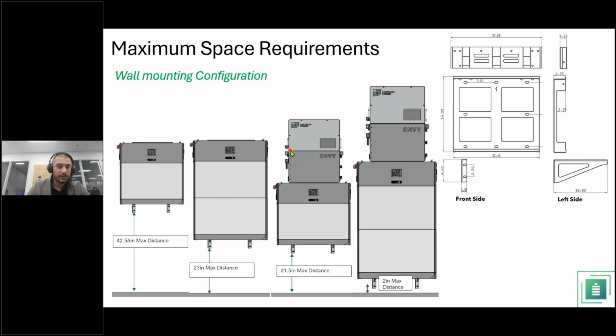So this would be your PV switch from the MV. If you do this measurement, if you install it in this way, this will guarantee that this disconnect is not going to surpass 6.7 feet as stated from the NEC code. And then if you're doing two batteries with an MV, same thing.